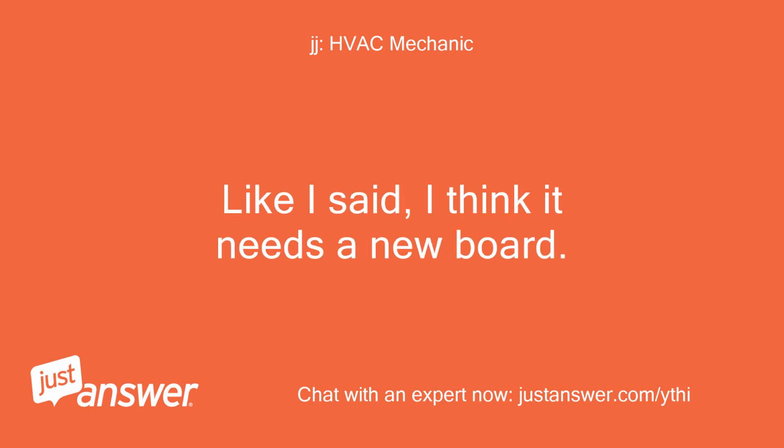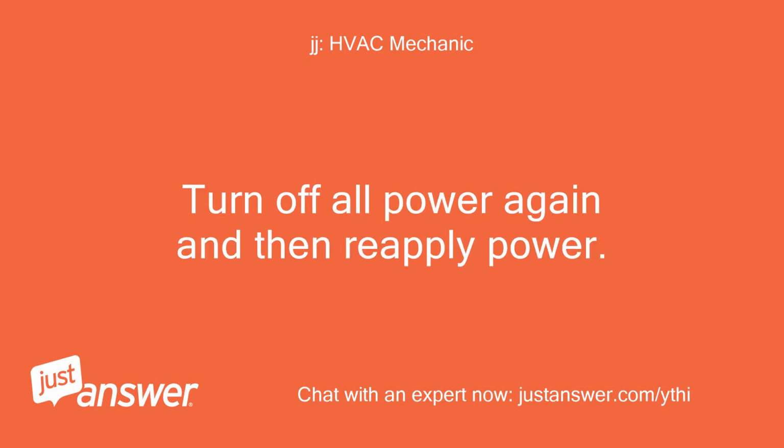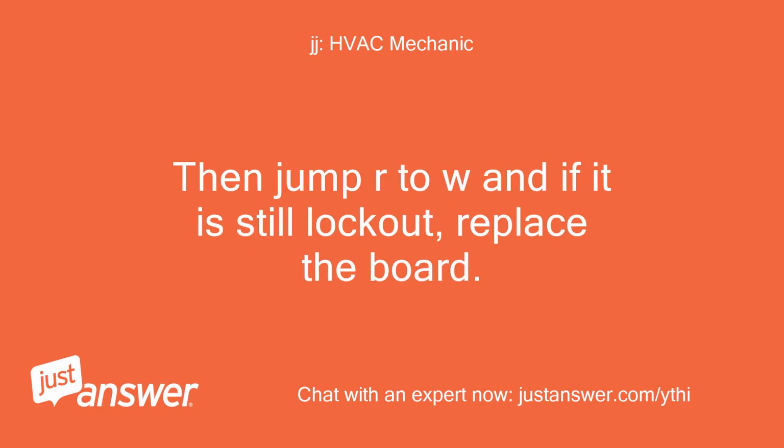Like I said, I think it needs a new board. Maybe they have a used one you could try. Turn off all power again and then reapply power. Then jump R to W, and if it is still in lockout, replace the board.